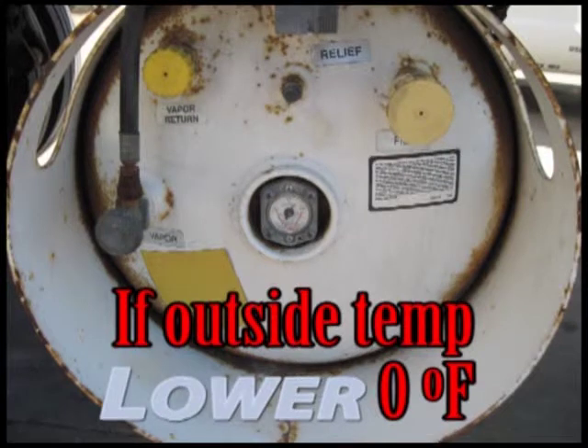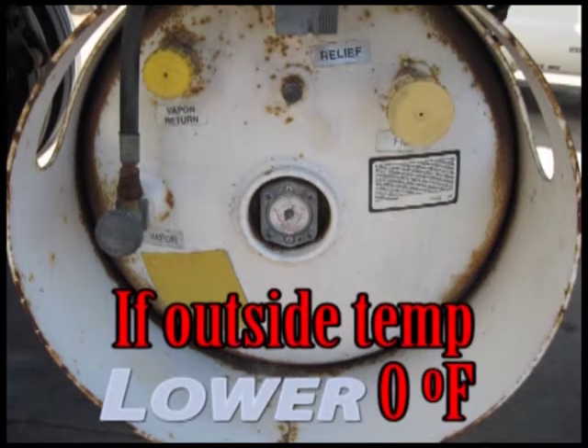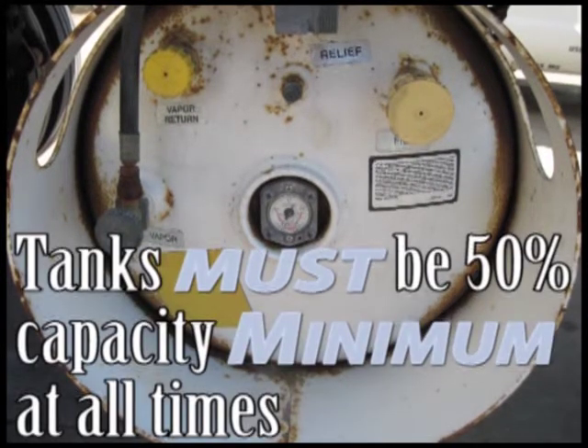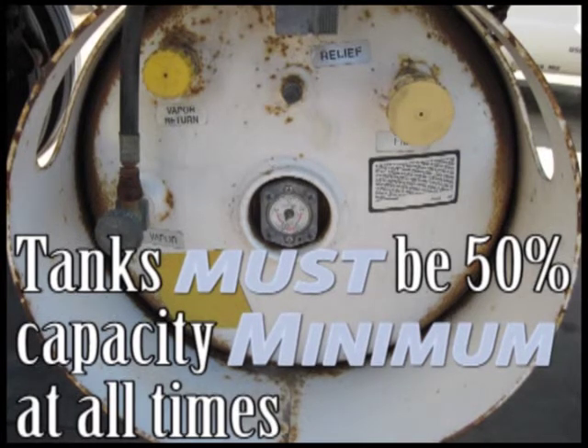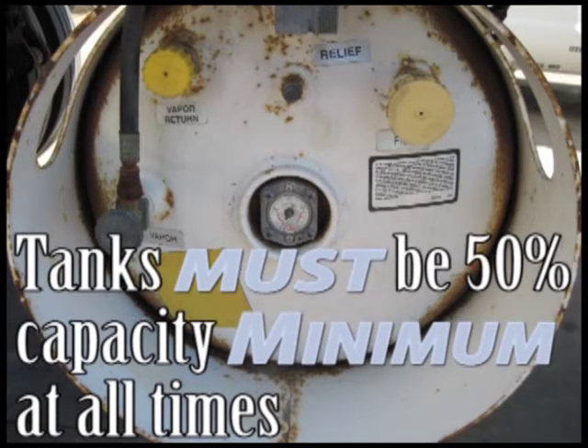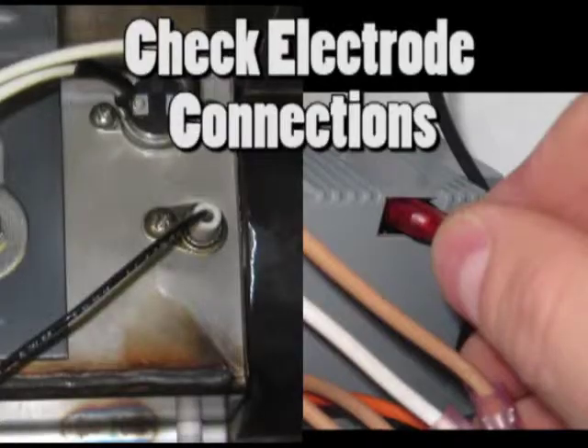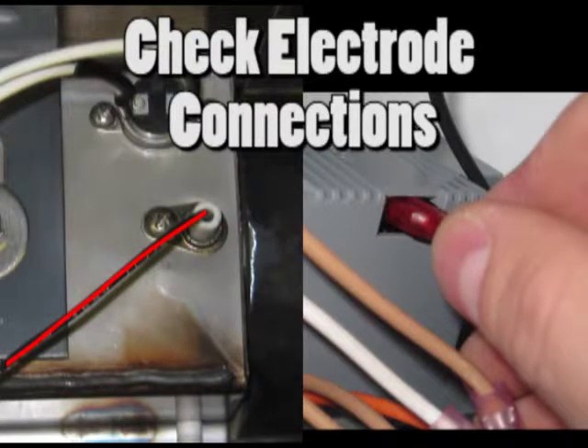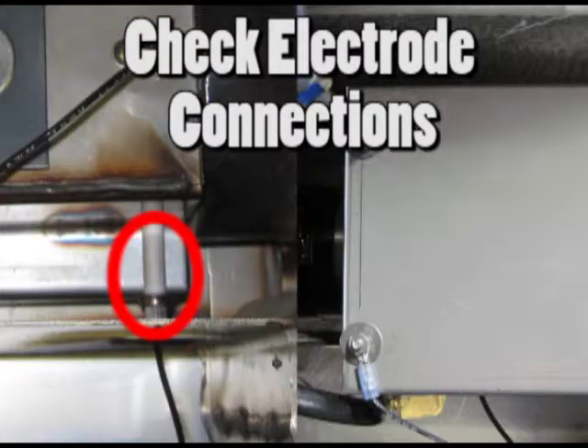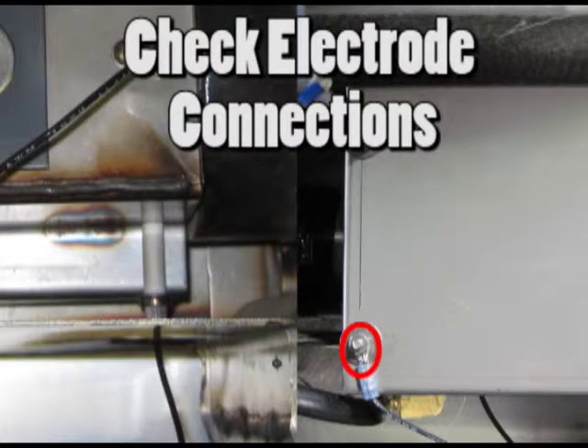Notice, if the ambient temperature outside is below 0 degrees Fahrenheit, the liquid fuel level of the propane tank must be kept at least 50% full at all times to ensure propane vapor can be produced fast enough to replace the propane being used by the heater. Check that the primary spark electrode's extension wire with the female quick connection is securely connected to the ignition module high voltage output. Check and verify that the secondary spark electrode extension wire with a number 10 ring terminal is grounded to the combustion chamber shell.